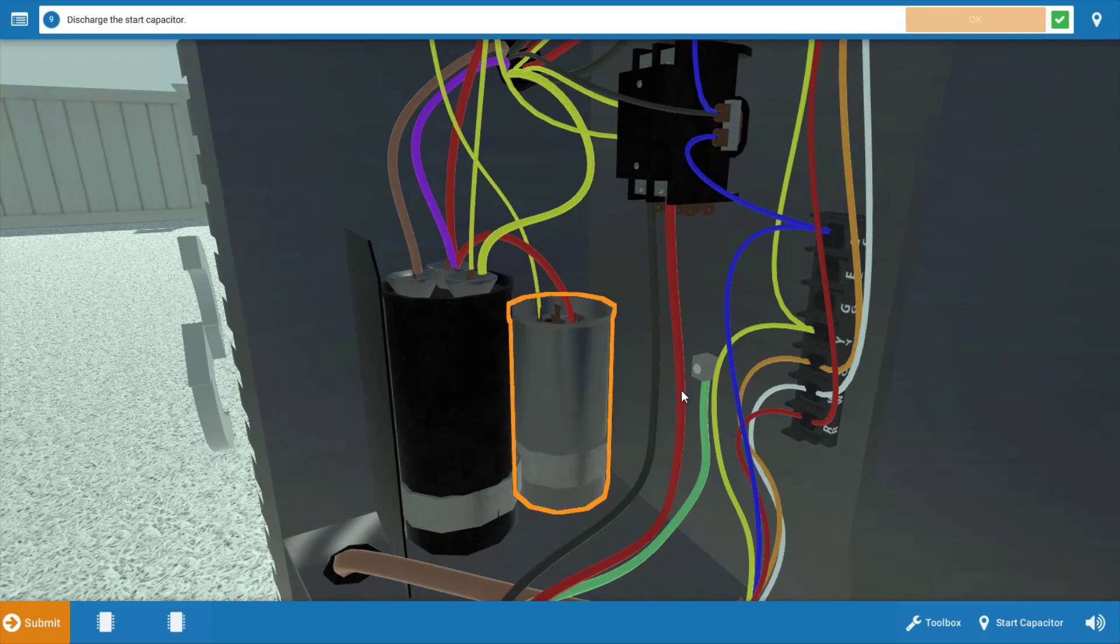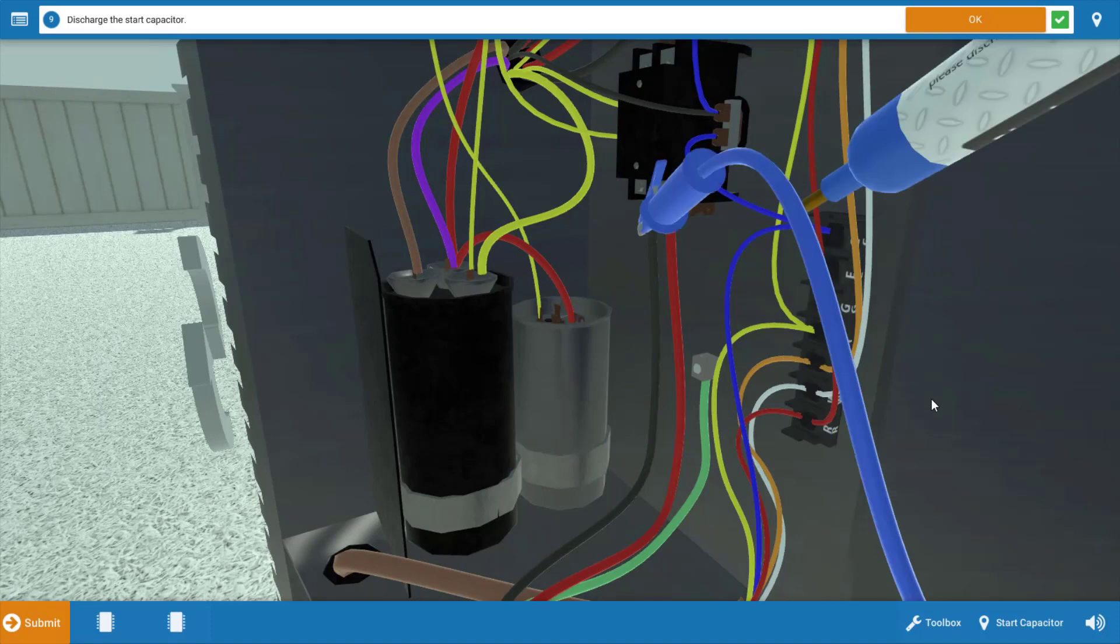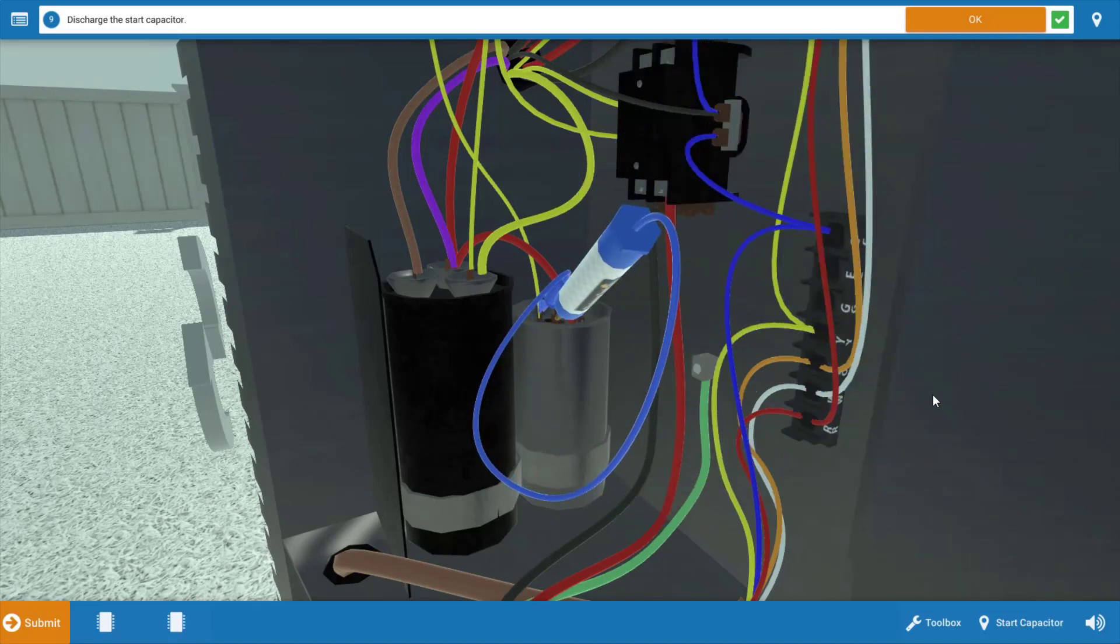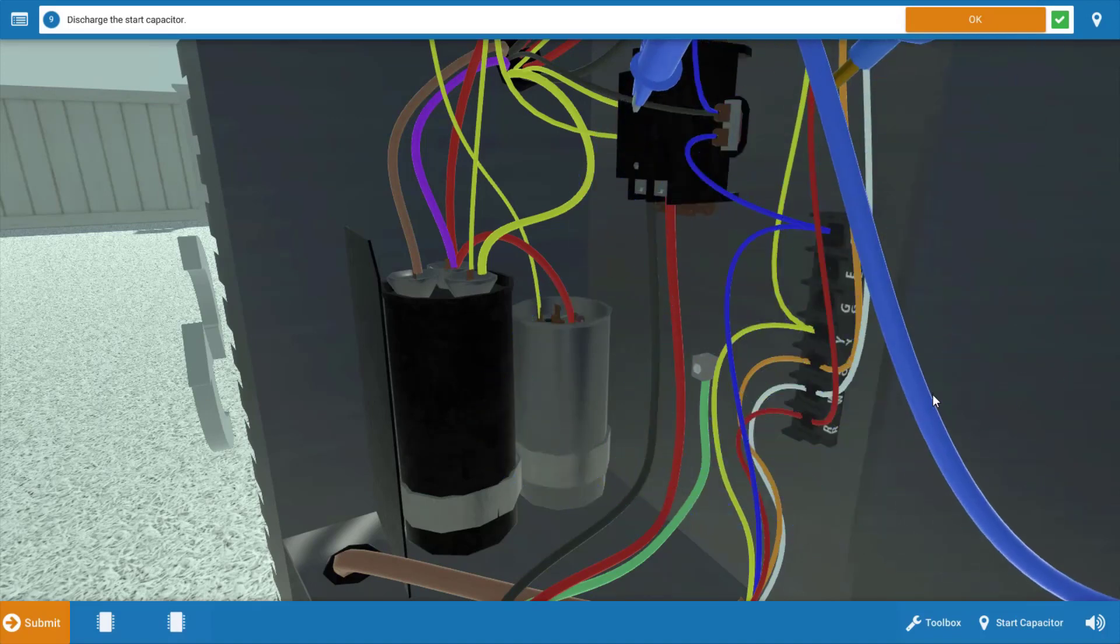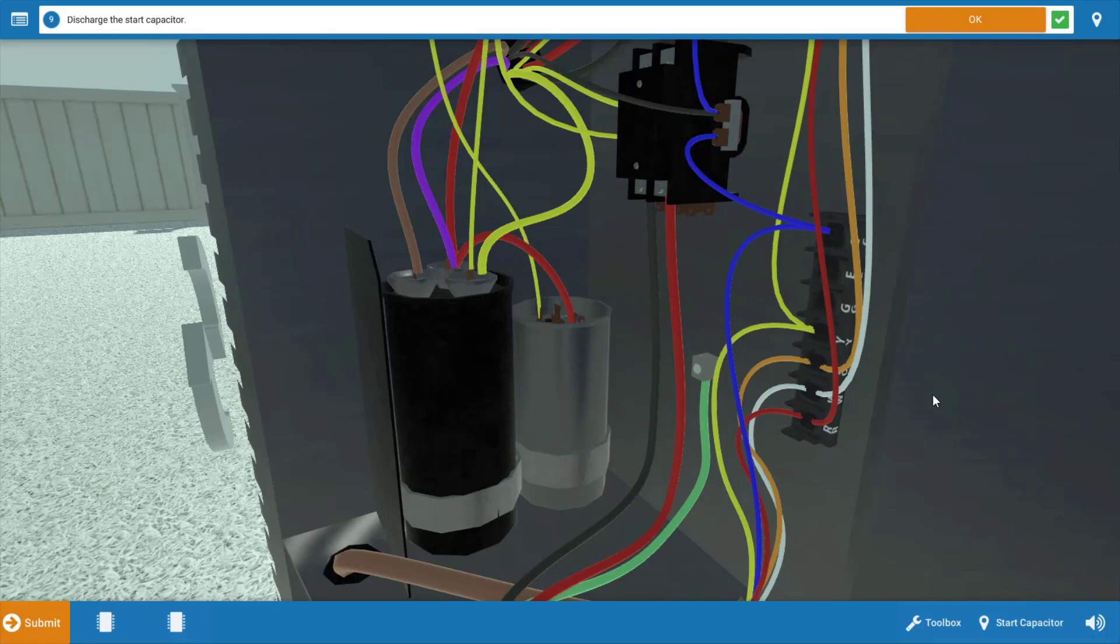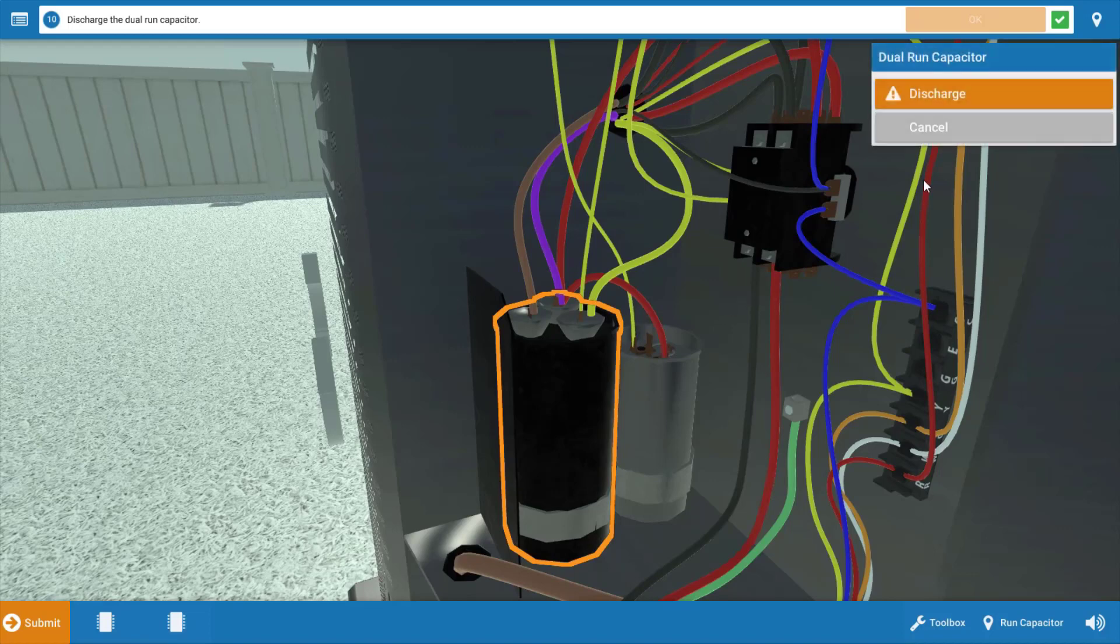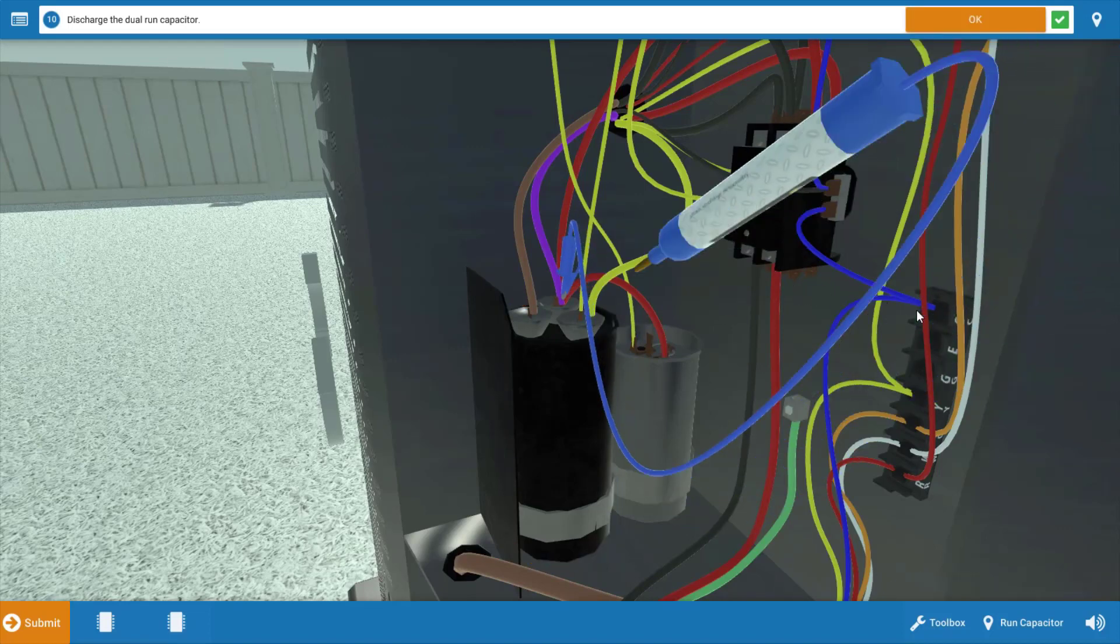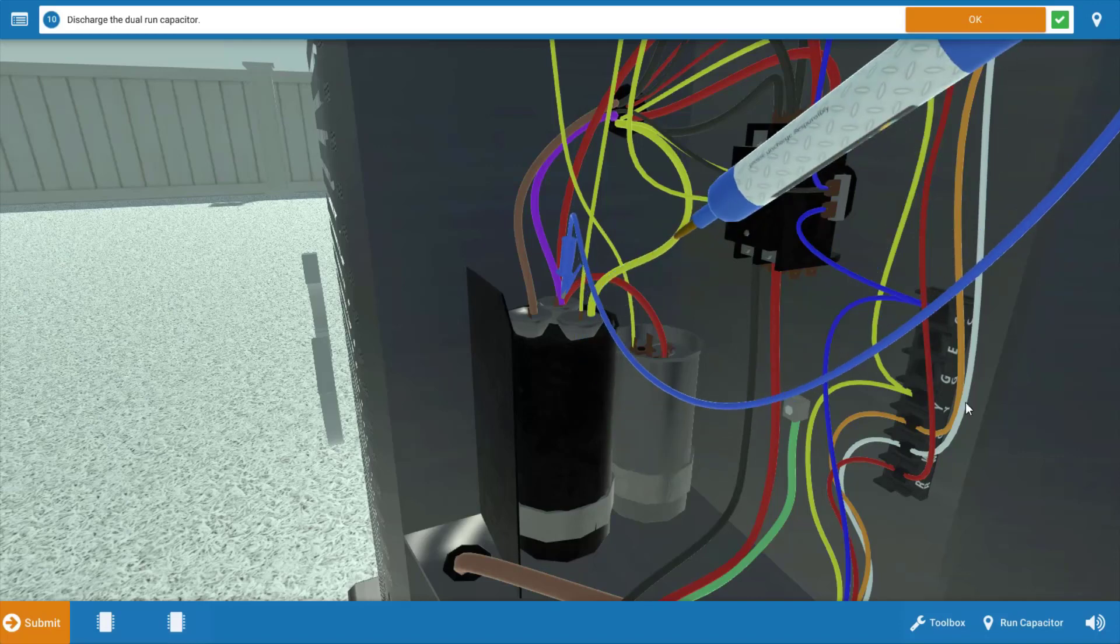Next, we need to discharge both capacitors. We're going to start at the start capacitor, click discharge, and we have a convenient little discharge tool. It's very inexpensive that you can pick up. I don't suggest discharging with a screwdriver. I know that's commonly done, but you do run the risk of damaging the compressor terminal with that arc. Click OK on the procedure guide, and next we're going to discharge the run capacitor. And again, once we've done that, we can isolate them.